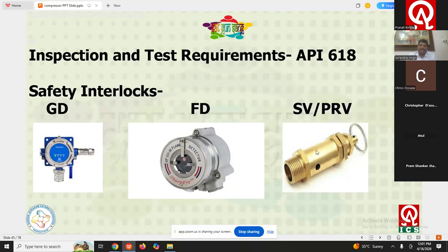For the safety valve or PRV, we need to apply over-pressurization. We give excess pressure, 125% or 130%, which is the setting defined in the QAP. Whenever the over-pressurization reaches 125% of the maximum allowable working pressure, this device automatically opens and the pressure is released from that area. So we need to check this during the inspection in line with the QAP requirement.